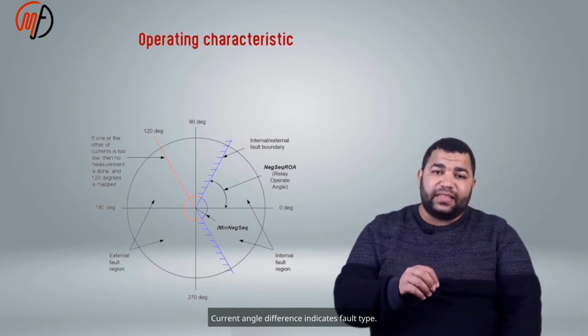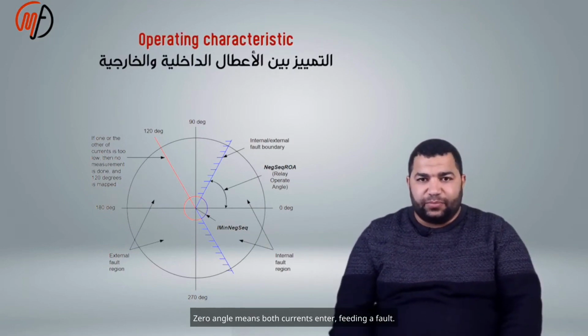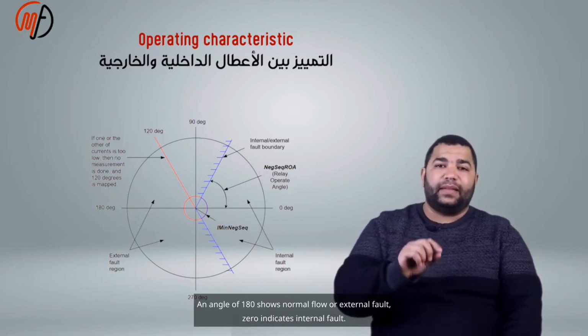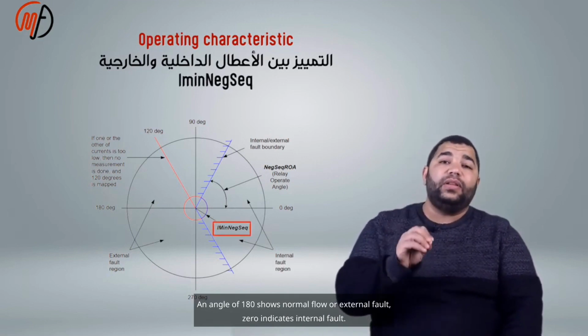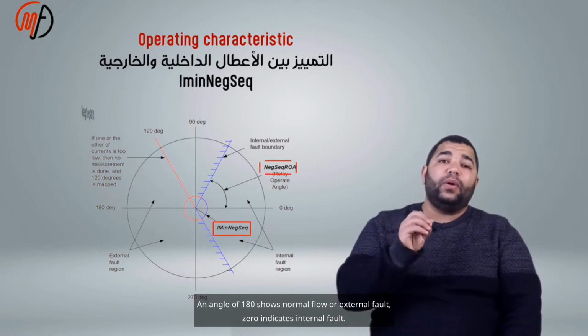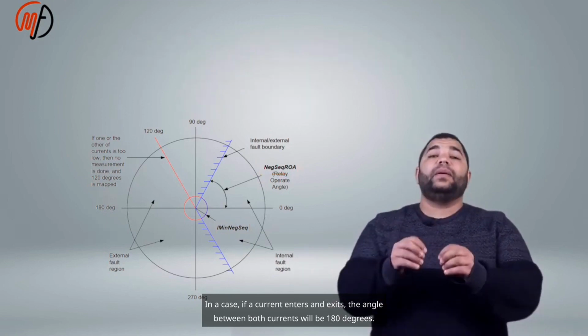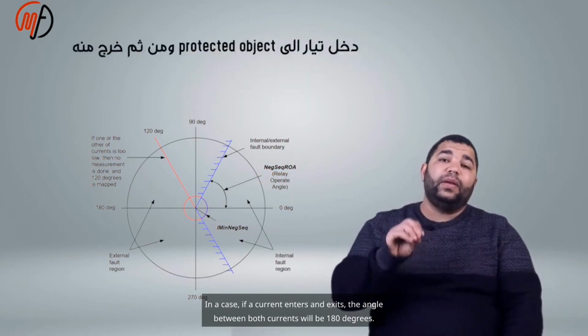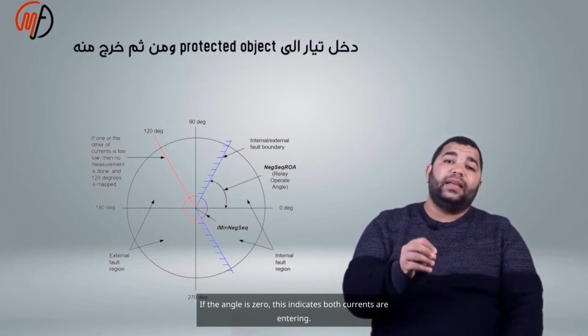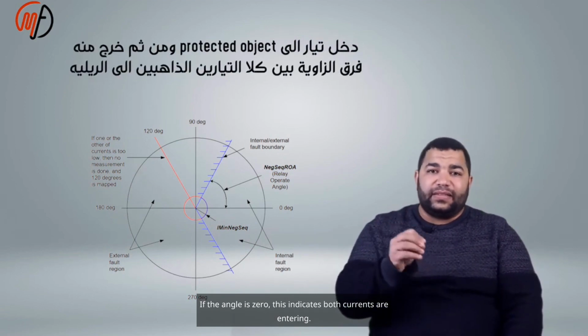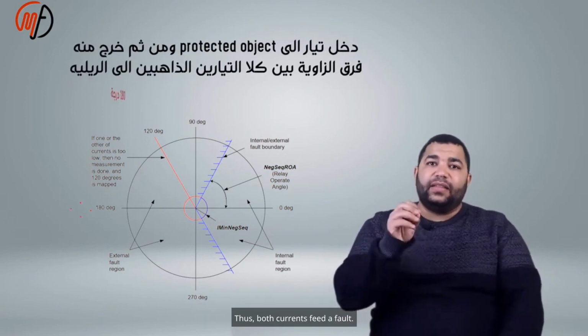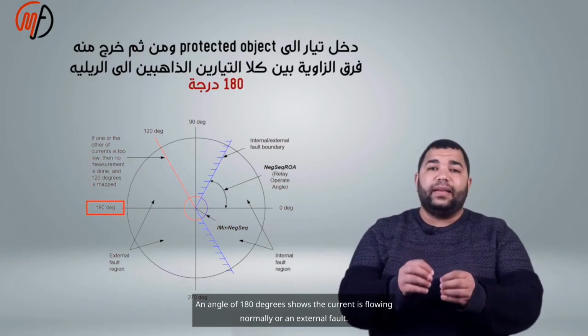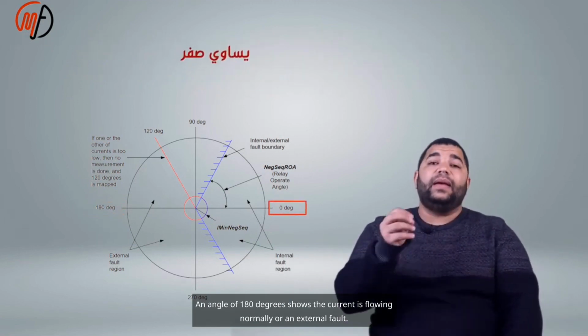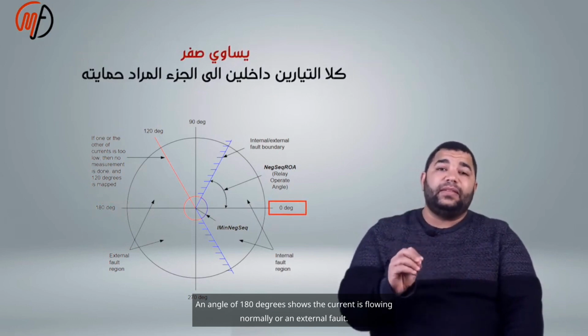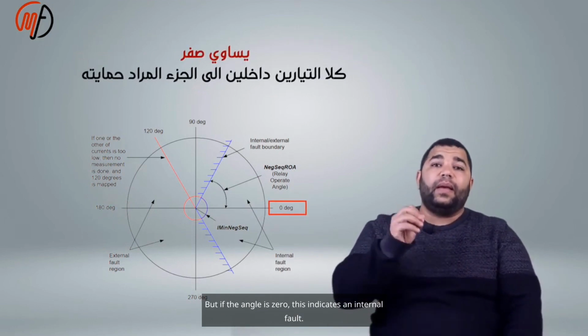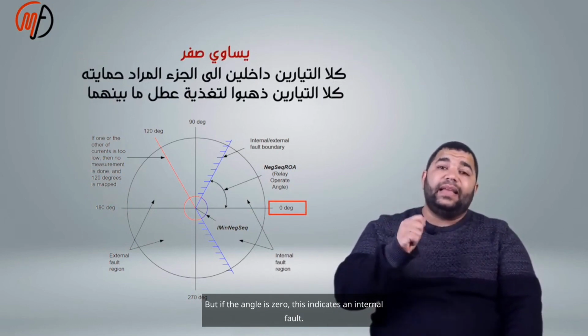The current angle difference indicates the fault type. An angle of 0 means both currents enter, feeding a fault. An angle of 180 shows normal flow or external fault. An angle of 0 indicates an internal fault. In a case where a current enters and exits, the angle between both currents will be 180 degrees. If the angle is 0, this indicates both currents are entering, thus both currents feed a fault. An angle of 180 degrees shows the current is flowing normally or an external fault. But if the angle is 0, this indicates an internal fault.